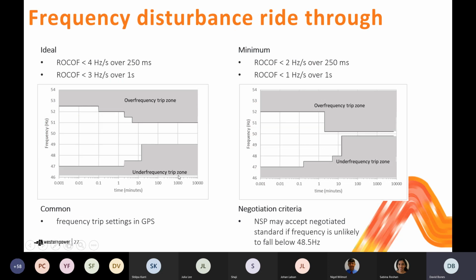The next series of slides we're going to look at discuss 5 performance standards that all place obligations on generating systems to ride through disturbances. Collectively, they each consider a different characteristic and the ability of the generating system to ride through that particular characteristic. So the first one we'll be looking at is the frequency disturbance ride-through performance requirement. And it really looks at the ability of the generating system to ride through disturbances that have a particular magnitude and duration of frequency being away from 50 hertz and a rate of change of frequency within particular limits.